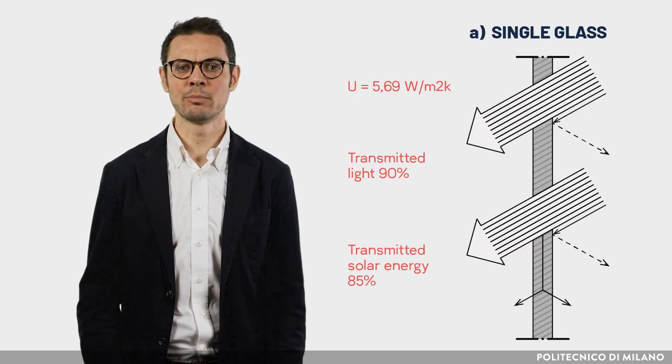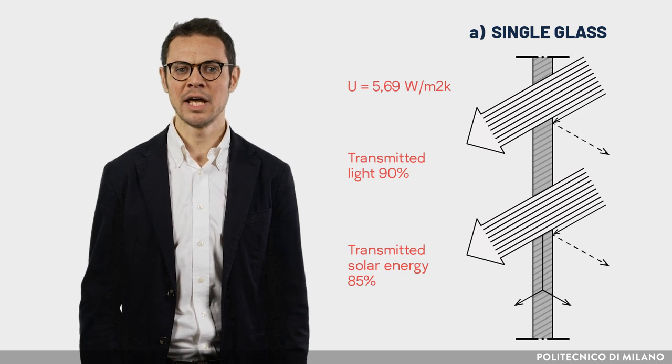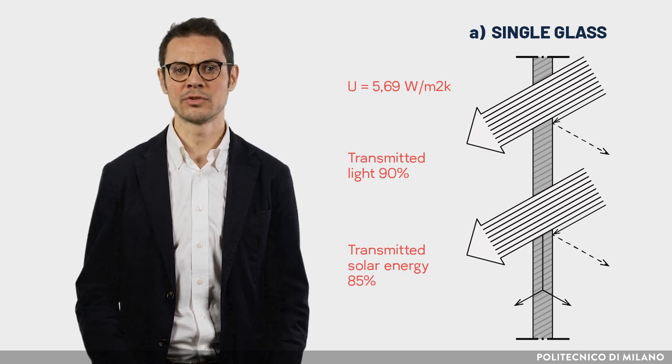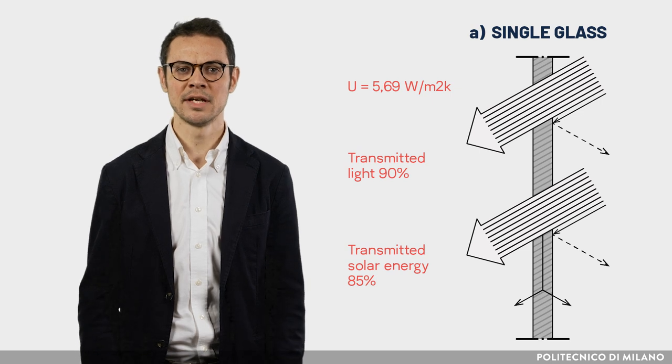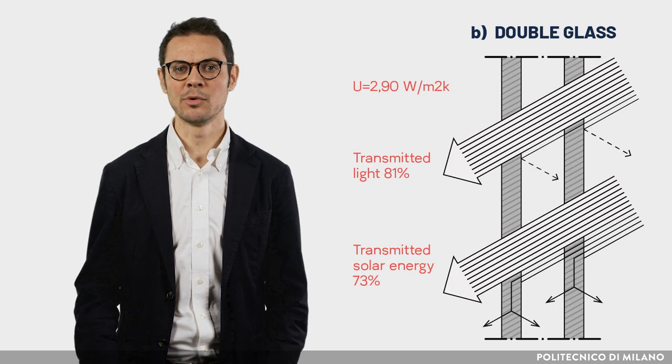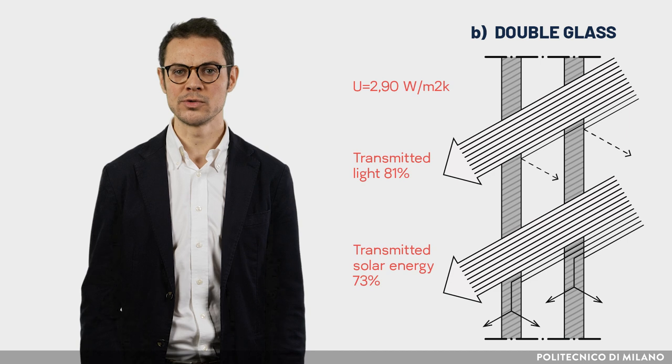Depending on the type of glass, the window is crossed in different ways by solar radiation, which can be considered both from the energy and from the light point of view. For example, generally a single glazing component is characterized by transmission in the visible spectrum and in the solar one of about 90% and 85%, respectively, while a double glazing has lower values.